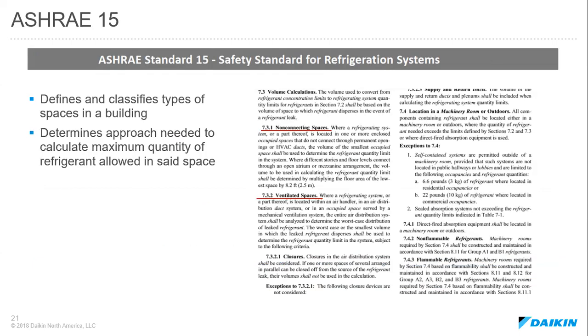So as I mentioned, ASHRAE 15 defines and classifies the types of spaces in a building, and it calls out the approach needed to calculate the maximum quantity of refrigerant allowed in said space. I've highlighted over here on the left just a copy of the code, and here you'll see it talks about things such as section 7.3.1, non-connecting spaces, and 7.3.2 talks about ventilated spaces and how the refrigerant systems should be set up and how they should be regulated.